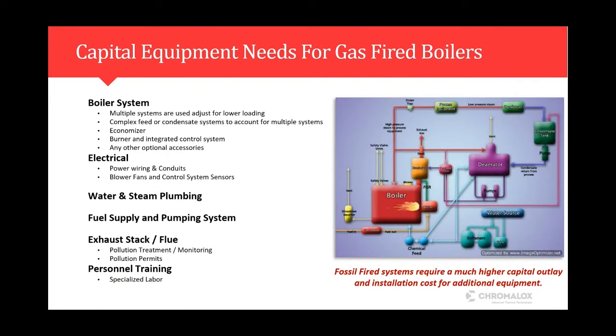And then, of course, the capital equipment. I've already mentioned all the infrastructure that's required to support the fuel-fired systems with the flue stacks and the oxygen metering, other chemical treatment that's needed. So even though the boilers themselves are traditionally lower cost than an equivalent electric system would be, all the infrastructure definitely helps to shrink that gap between the cost of the actual electric steam generator itself, because there's just a lot more that's required to get these systems up and running.